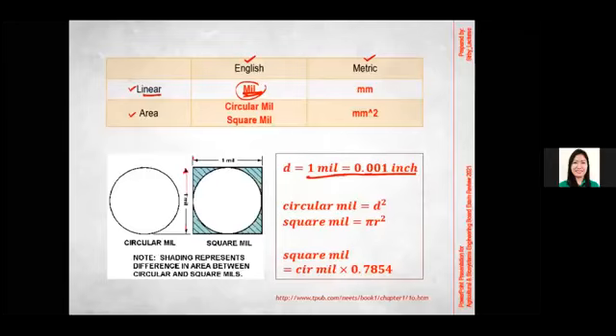In terms of area, we can have a circular mil or a square mil. For circular mil, it's basically the square of the diameter, or the area in terms of a circle. When we talk about square mil, that's the area of a square. We can see in the figure that the square mil is larger than the circular mil, and the difference is this shaded, blue area.